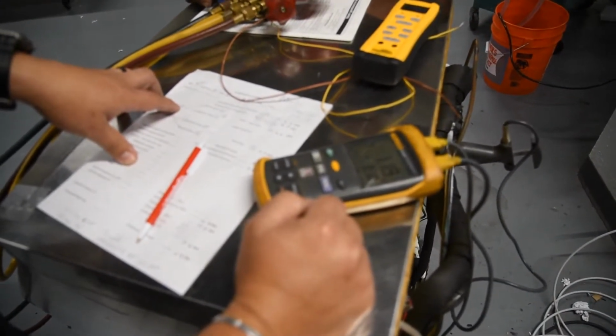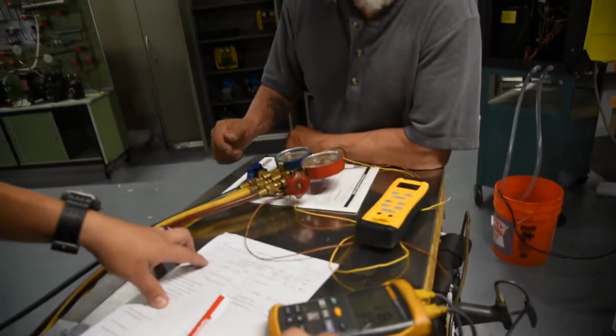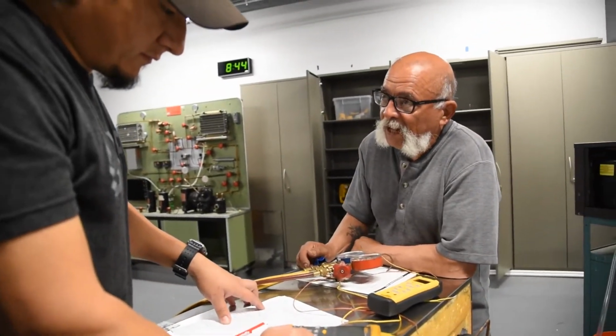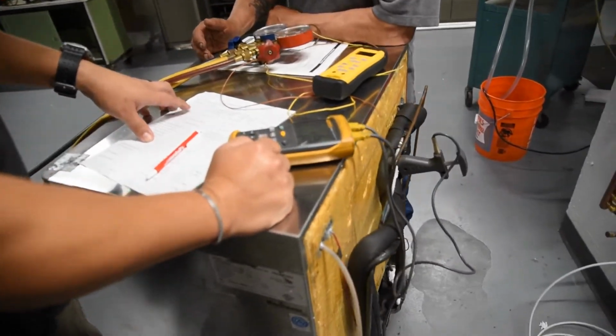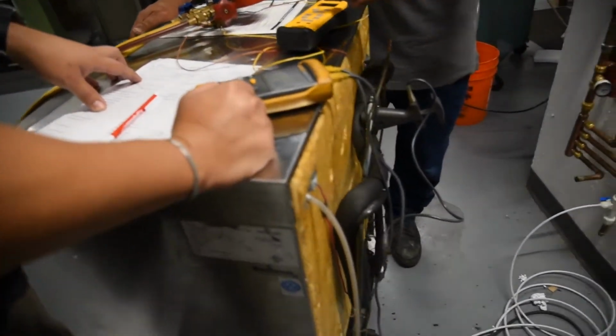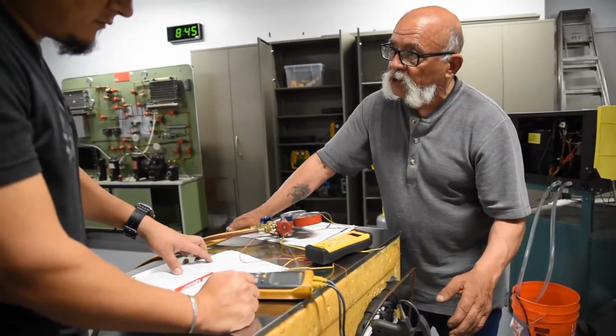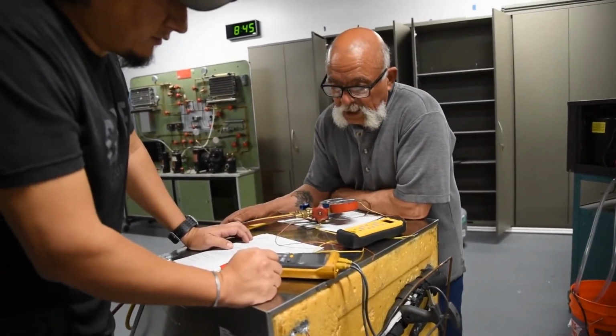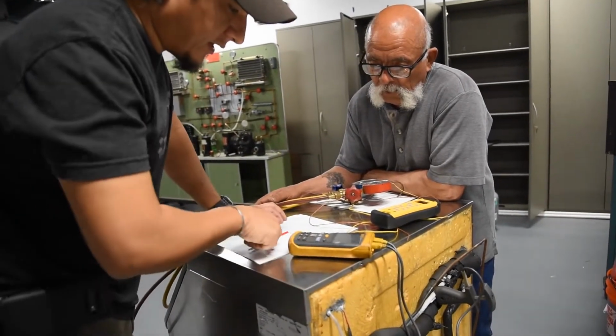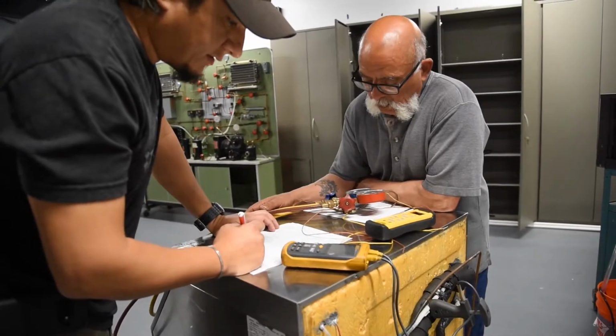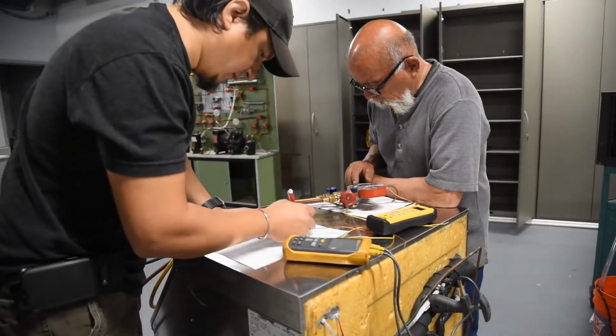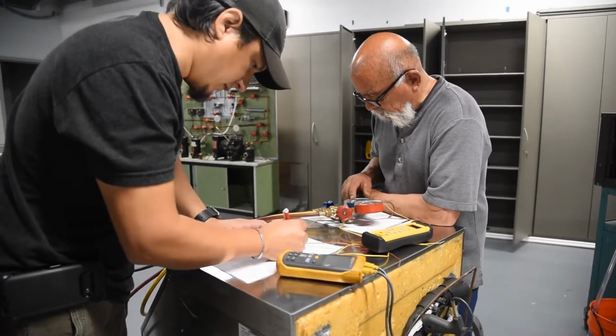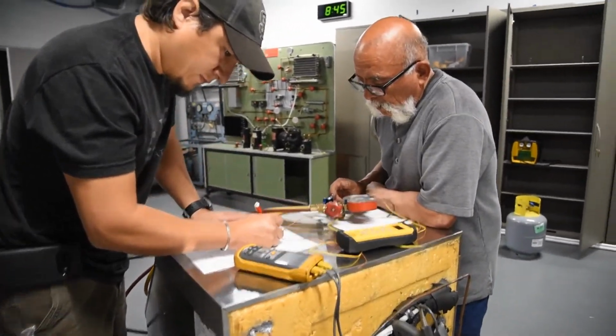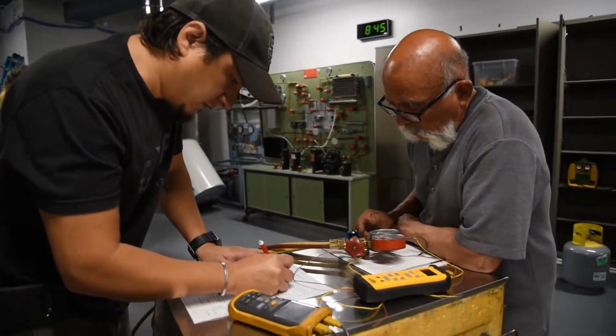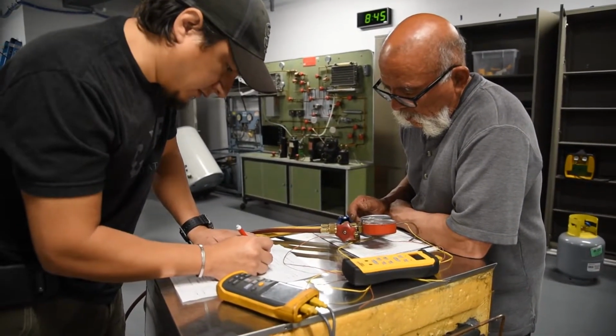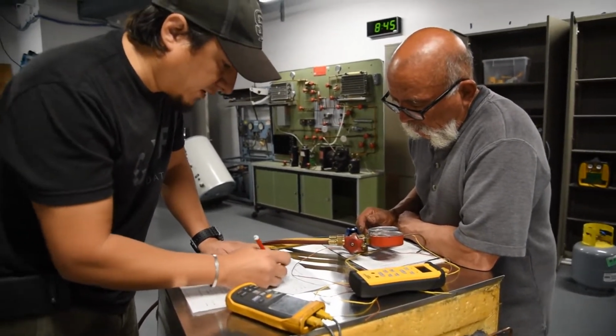Yeah. If you don't use your instruments correctly, we gather bad information. We're going to make a bad decision on what we have to do with the machine. So before we do anything, like you did, we check to make sure all our instruments are working correctly. Now what do we got? Okay, now we got 10.5 degrees. And the low side temperature is about 5 degrees. So now we have 5.5 superheat.